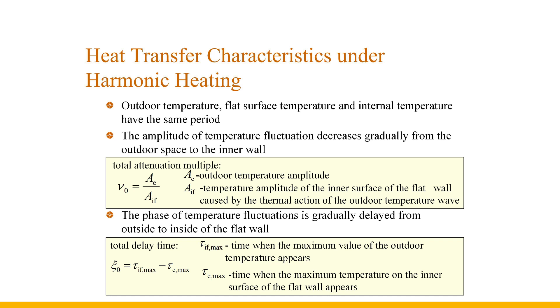Third, the phase of the temperature fluctuation is gradually delayed from the outside to the inside of the flat wall. This phenomenon is called the phase delay of temperature fluctuation — that is, the moment when the maximum temperature occurs is delayed. The total delay time of the flat wall refers to the difference between the time when the maximum outdoor temperature appears and the time when the maximum temperature on the inner surface appears.